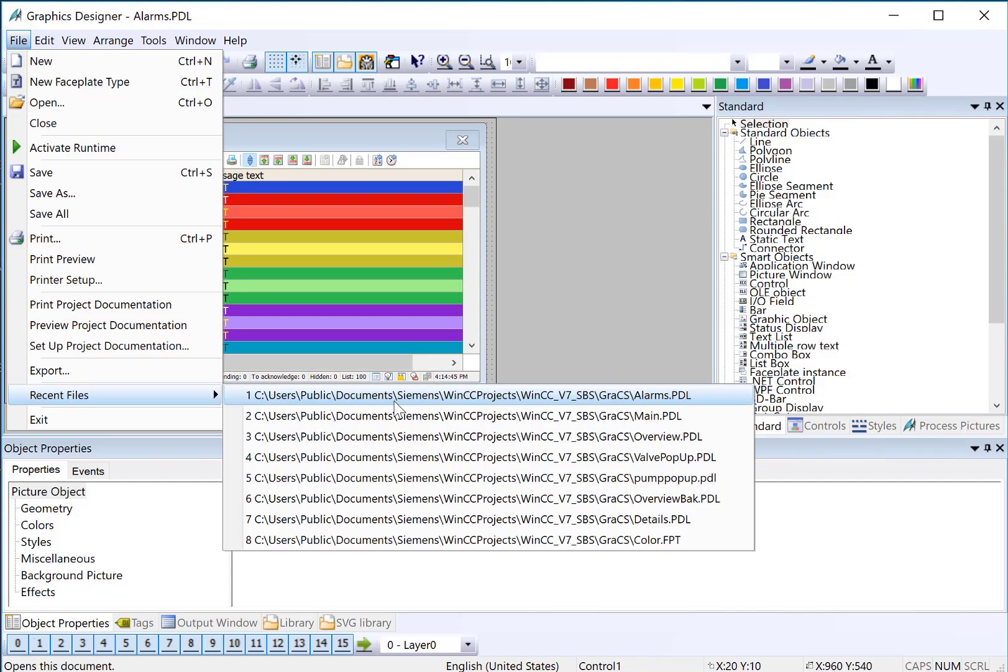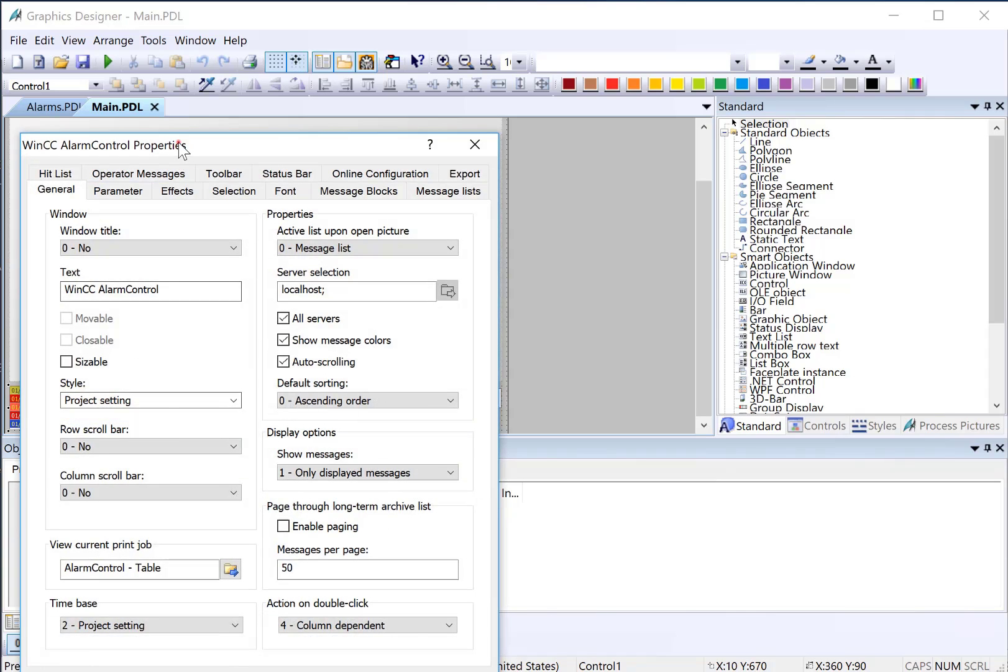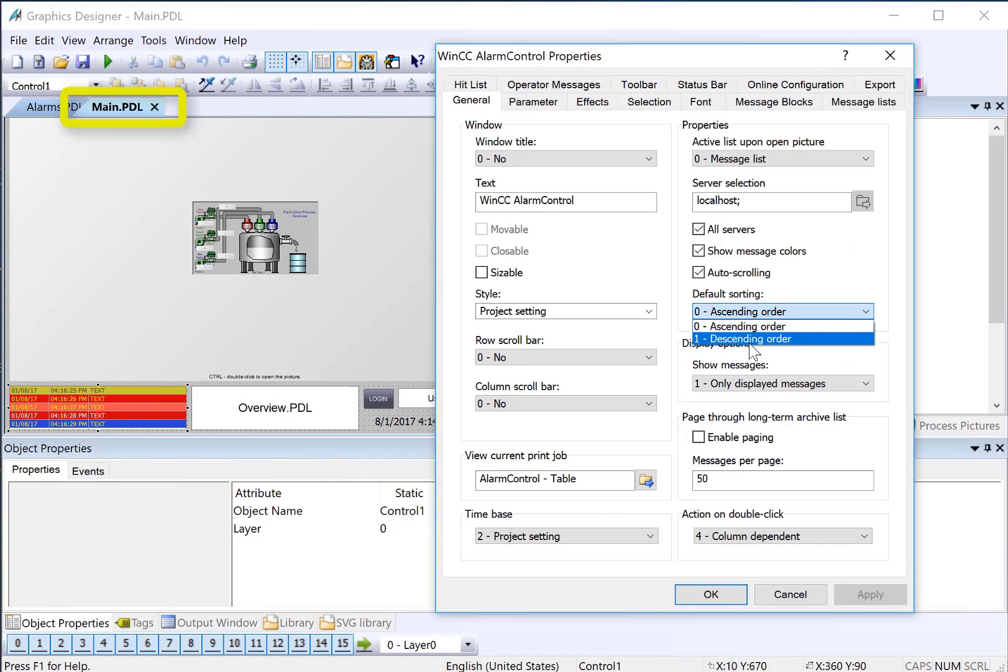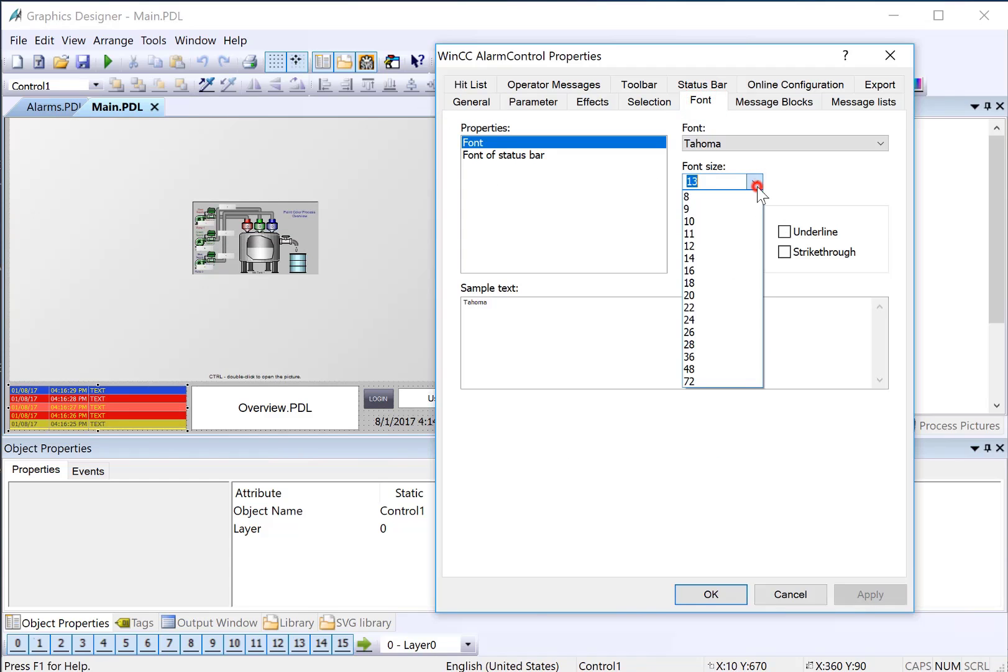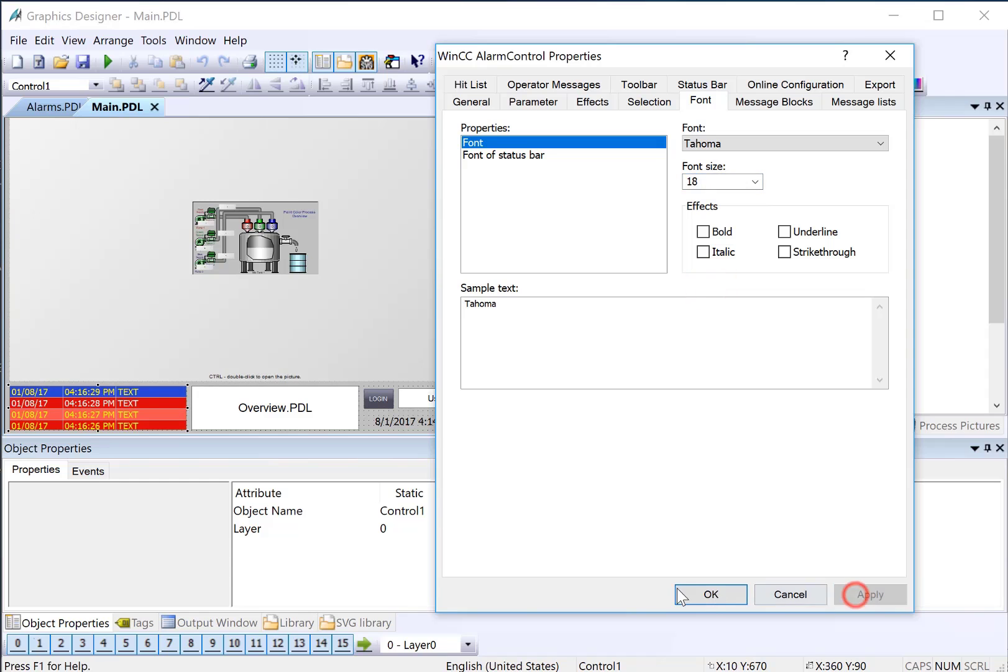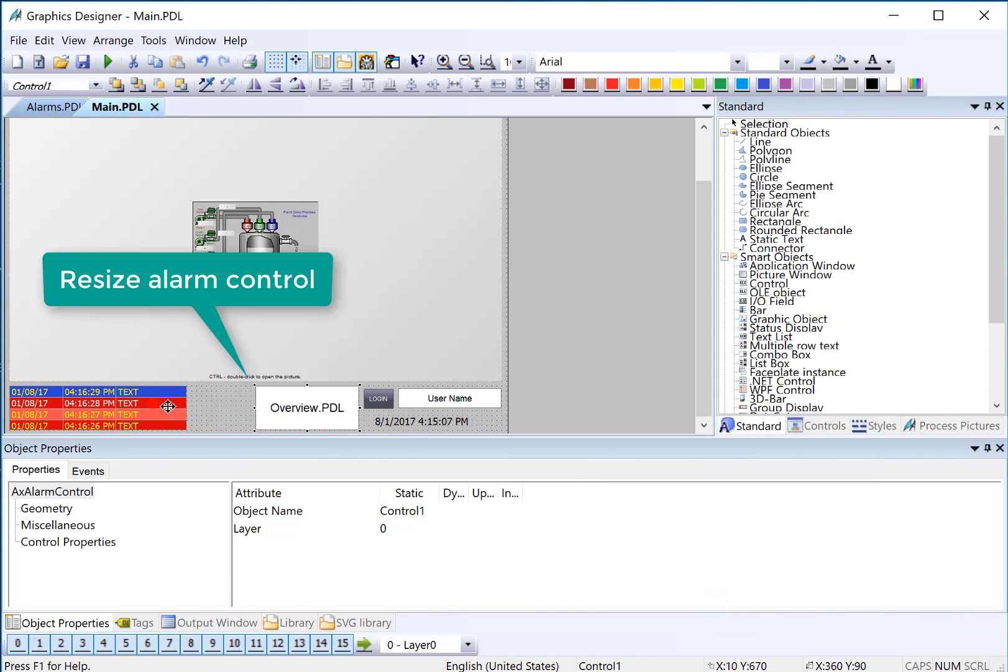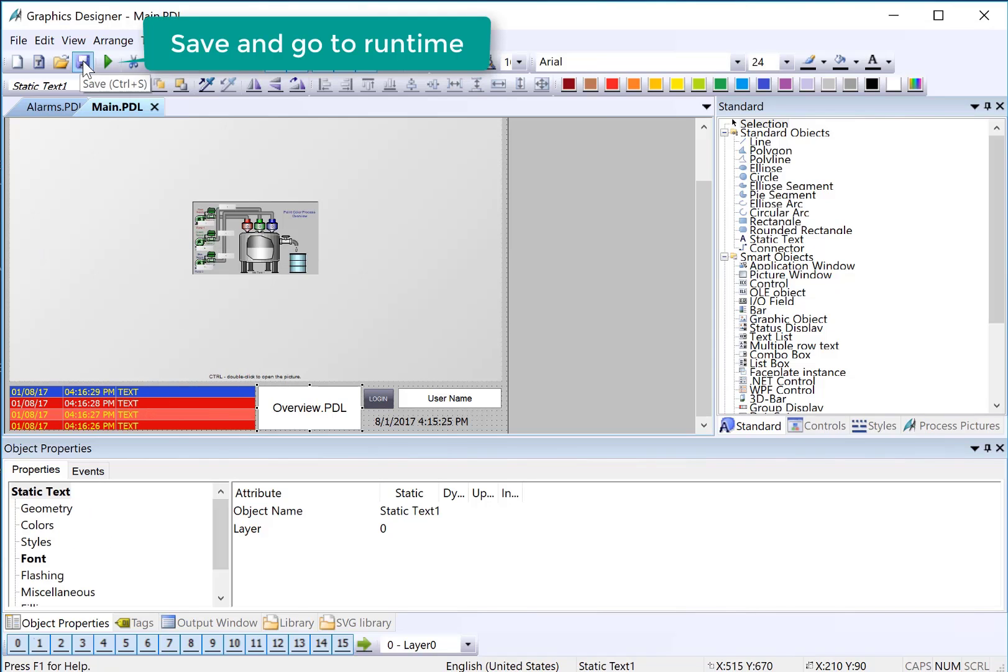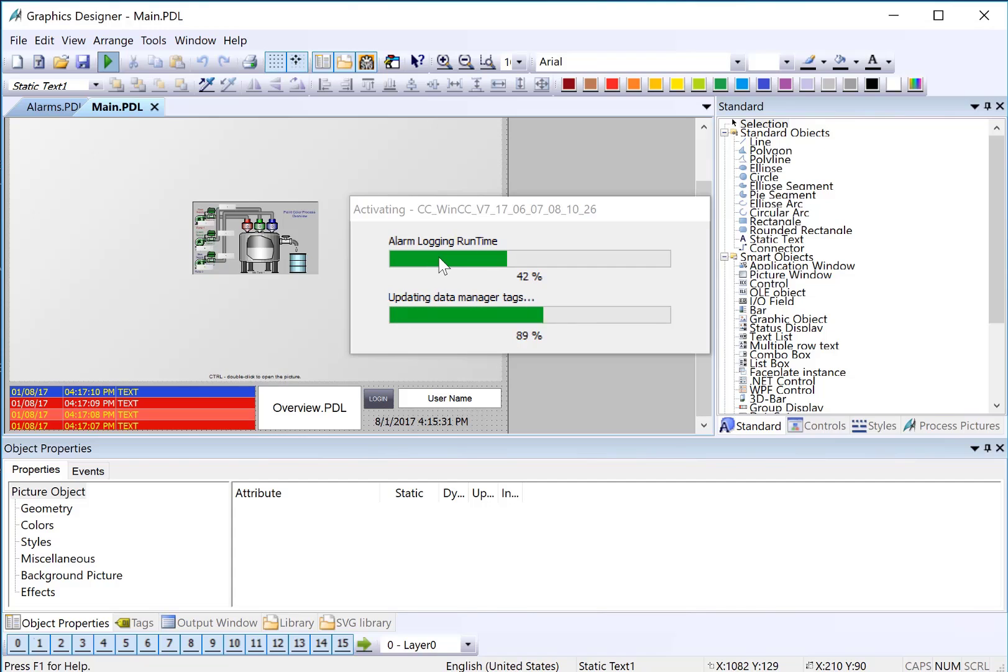And I want to open my main screen. Double-click on my alarm banner there. We'll change our default sorting to descending. And on Font, we'll also increase the font size. And I'll make a little room here so that we can see the remainder of the text message. Then I'll click Save. And then we'll just go to Runtime to test. And when we're going to Runtime, you should see the Alarm Logging Runtime Editor being activated. And this is because we turned it on in WinCC Explorer.